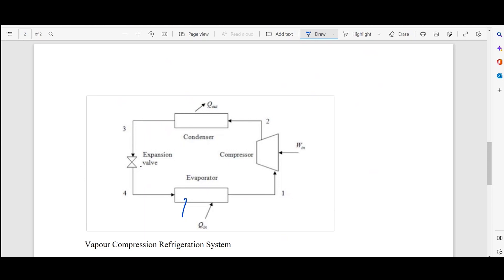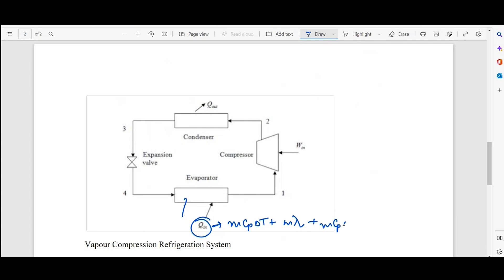After the compressor, the fluid passes through the condenser, where the absorbed heat is removed and released into the atmosphere, followed by expansion where pressure reduces again. The heat absorbed from the material is called the refrigeration load or refrigeration capacity, equal to m·Cp·ΔT. If this heat load includes freezing, latent heat is added, and if temperature is kept below freezing, another m·Cp·ΔT term below the freezing point is added.